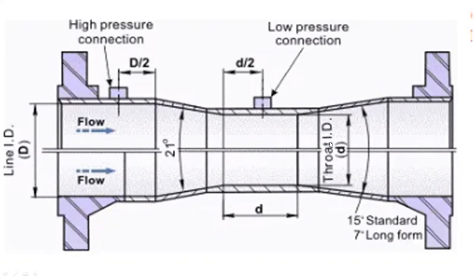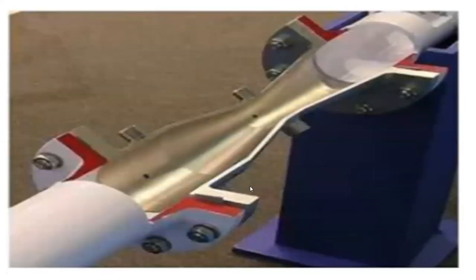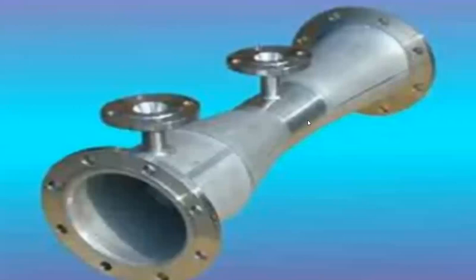In the diverging conical section, the tube diameter gradually increases, so the pressure builds up again to the original inlet pressure. The cone angle is five to seven degrees, and 15 degrees is standard for the outlet cone. Small size venturimeters are made of brass, glass or bronze, and large venturimeters are made of cast iron, steel or stainless steel.